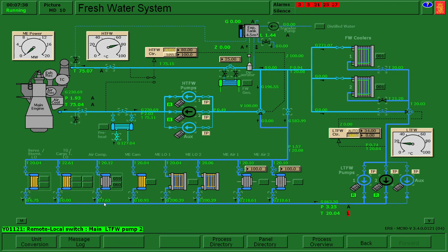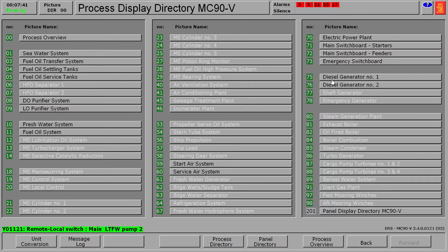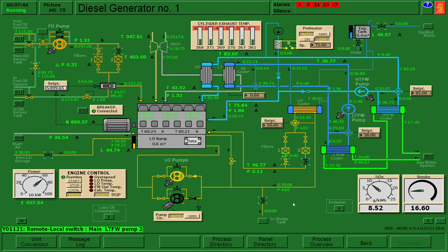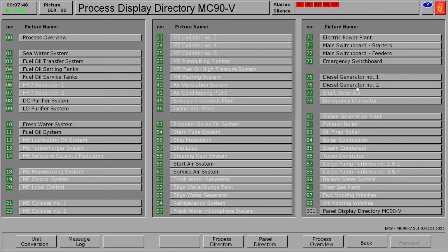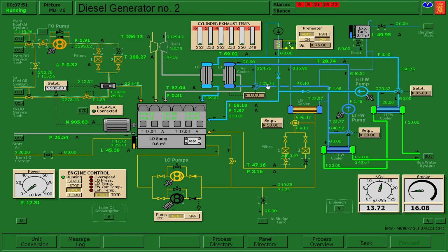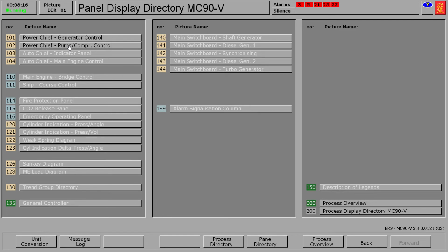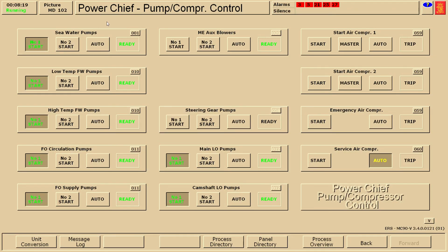And then we're gonna monitor both generators. Diesel generator number 1, we're just gonna monitor, and we're gonna check also diesel generator number 2. Okay, so as you can see, the alarm here, it already is stable, so there's no more alarm. Okay, so if there are no problems, we're just gonna proceed to our panel directory, MD102. Okay, our pump control.